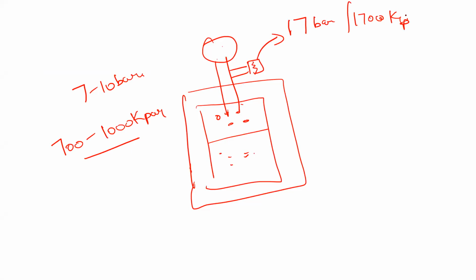Able to follow so far? Yes, sir. Okay, so this is liquid oxygen. These are the vapors. The vapor pressure is normally kept between 7 to 10 bars, and the safety relief valve opens when the pressure extends beyond that. So when you don't utilize the liquid oxygen for quite a long duration, what happens? Vapors will be formed and it's going to over-pressurize. So at 17 bars, this safety relief valve will open so that the liquid oxygen tank is protected.